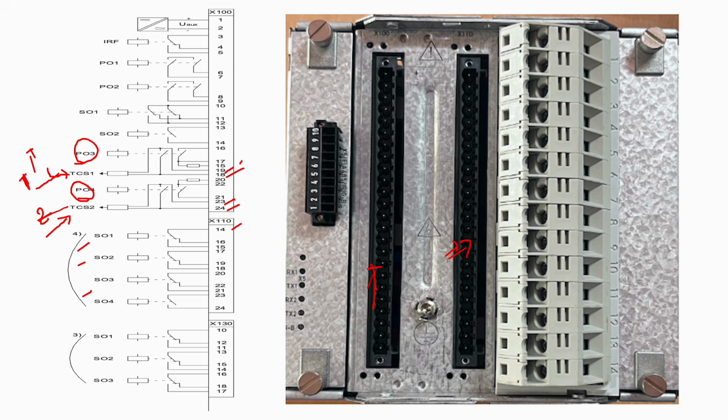Here 18 19, you connect your TC1 trip coil, and 23 24 you can connect here TC2, negative return negative in this particular section, then this relay will give you continuous monitoring of your tripping coil. If your tripping coil is unhealthy, the RET will give you an alarm. If it is healthy, then everything will be okay.